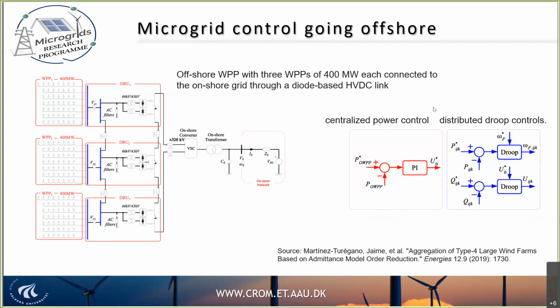It's interesting to see how they also use classical microgrid controllers: distributed droop controllers, with the classical frequency versus active power droop to share power between wind farms, and reactive power versus voltage droop to share reactive power compensation. Then there's a centralized power controller, normally used in secondary or even tertiary control, just to fix the amount of power you want to inject from your offshore wind power plant to the main grid.